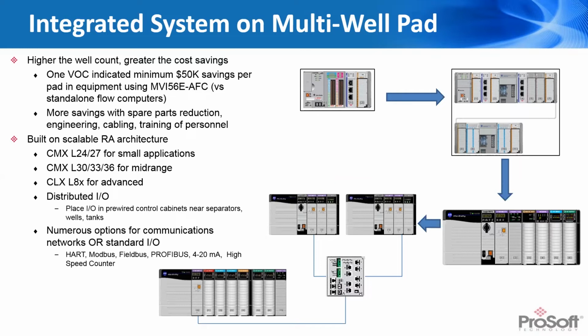With the scalable architecture of Rockwell, you can start out with something like the Compact Logix L24 or L27 for smaller applications, skid-based LACT systems, or skid-based compressor applications - all done on a low-end Compact Logix. Whereas if your automation needs, memory, and I/O counts increase, you can jump up to something like the L30, L33, L36 Compact Logix processors, which give you a lot more memory and I/O capabilities, while still supporting those measurement-related applications.